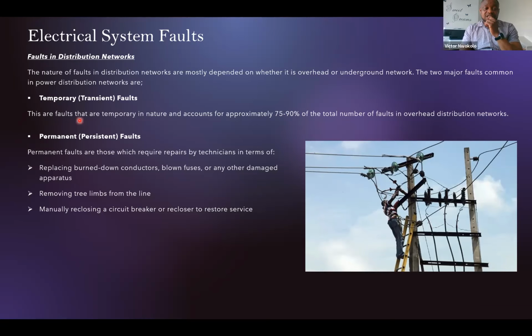So a simple transient fault that would have been cleared by a correct protection device within a few seconds can easily become a permanent fault that will require a repair team to be dispatched to locate the fault. And this happens when the protection system or the protection devices or the protection scheme is not correctly doing its job. So we'll touch on that when we're looking at how to clear faults.